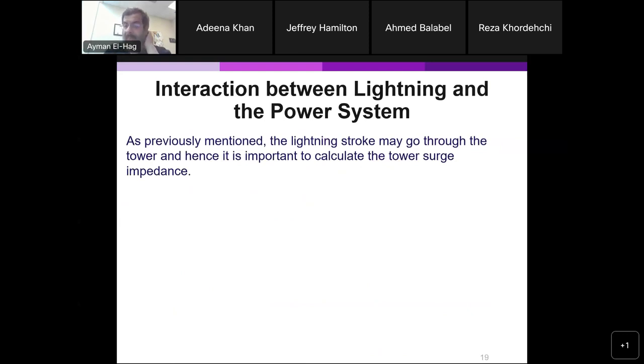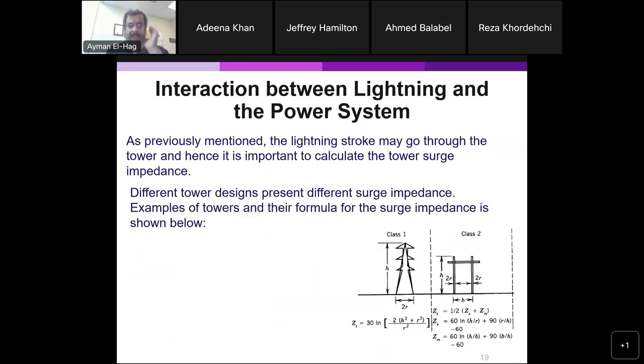Okay, now, as we mentioned, when the lightning strikes, it might go through the tower. Sometimes it doesn't go through the tower, sometimes it does, depending on where it hits. Every tower design will have a different surge impedance. So if the surge hits the tower itself, it will see a certain surge impedance. So it depends on different things.